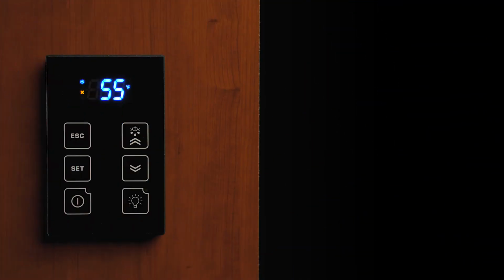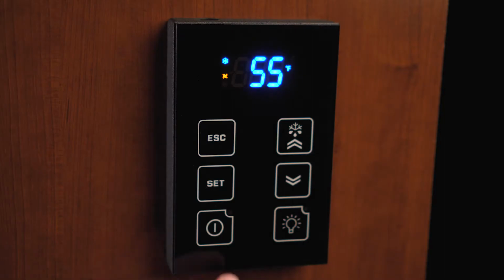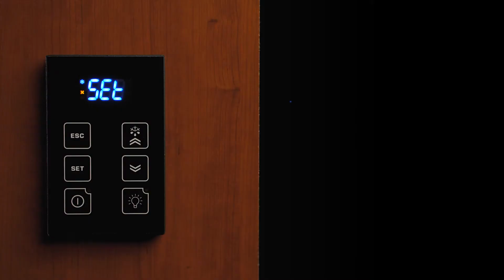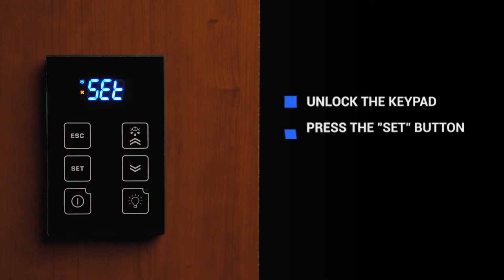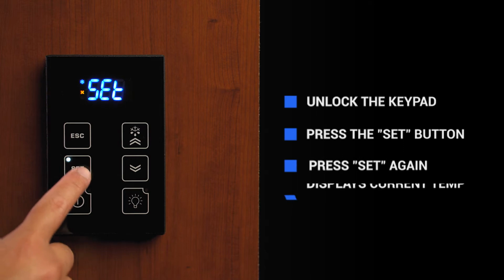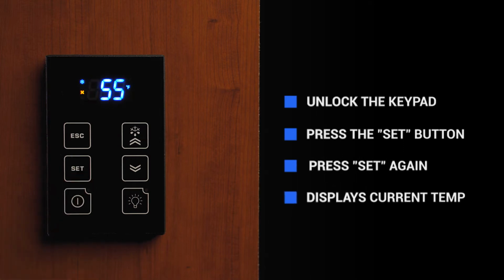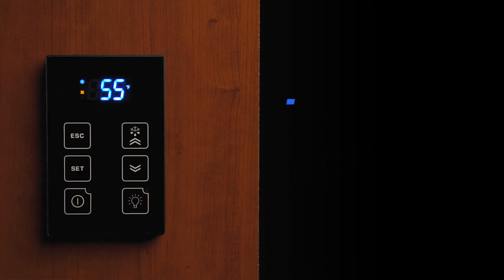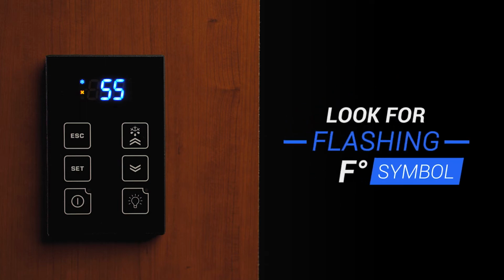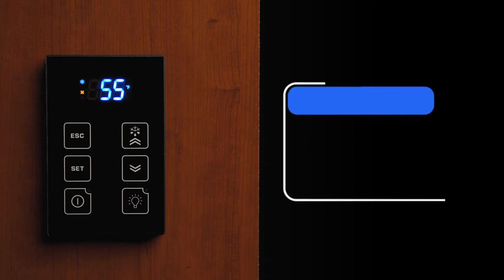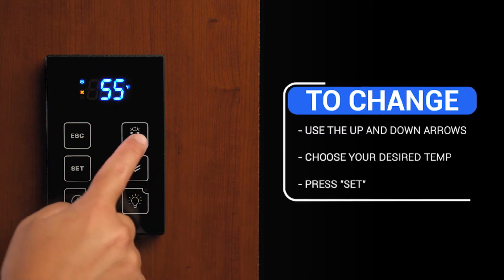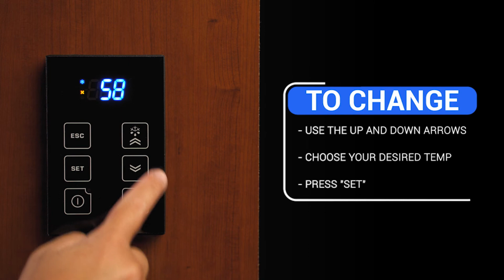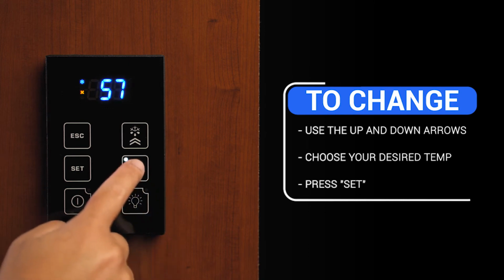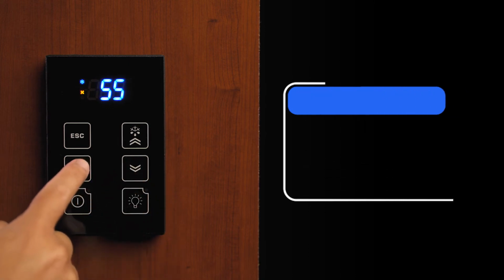To verify or change the set point, you will need to unlock your keypad, then press and release the Set button. Set will be displayed. Press and release the Set button again, and the temperature shown is what the unit is currently set to. The F symbol will flash, indicating that the set point is ready to be changed. If you want to raise or lower the set point, then use the up or down arrows to the desired temperature and then press Set to lock in that change.